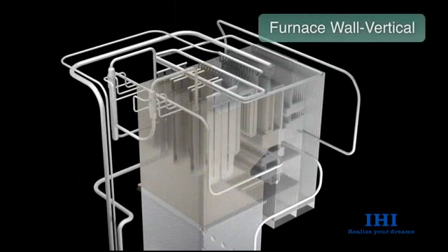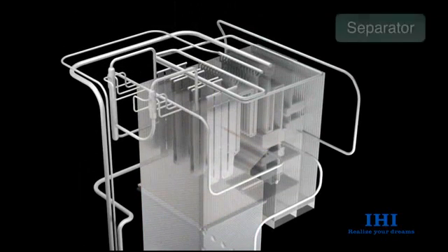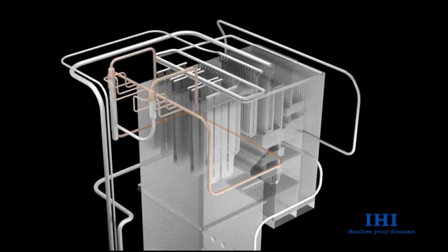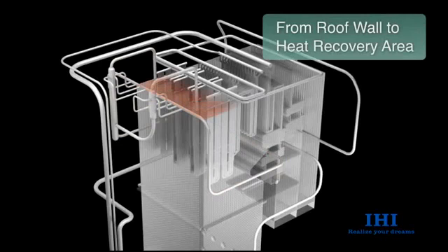During the low load operation of the boiler, the fluid at the inlet of the steam separators contains water and steam, which are separated by the steam separators. The steam from the steam separators is sent to the heat recovery area through the furnace roof wall tubes.